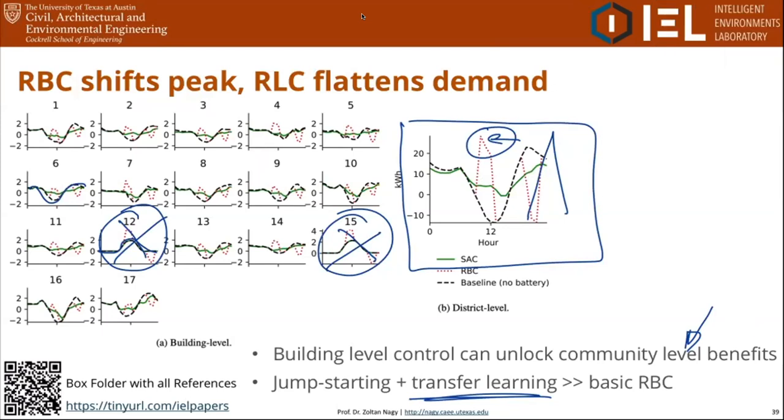Definitely in our work on the controls of these systems, you can end up with poor behavior. And the poor behavior is oftentimes manifested not in the building performance, what's observable in the building, but really in the equipment performance. It's really easy to end up with limit cycles, where you have the compressor at maximum speed, minimum speed, maximum speed, and all the valves oscillating. This actually happens very commonly with a lot of today's equipment, across probably almost all manufacturers, to be honest. So the performance is not that good, and the equipment lifetime can be compromised pretty significantly if you have bad controls. But you're not really seeing that.